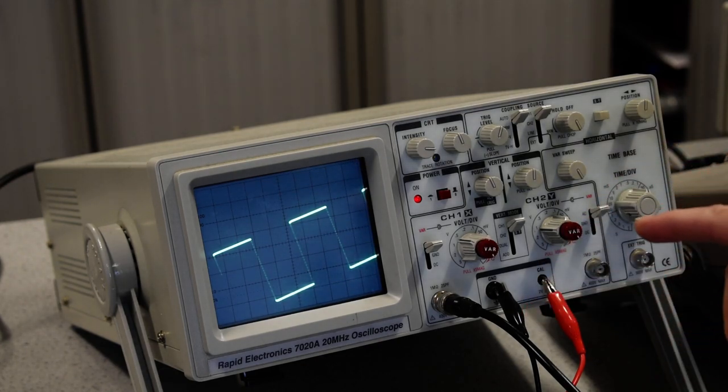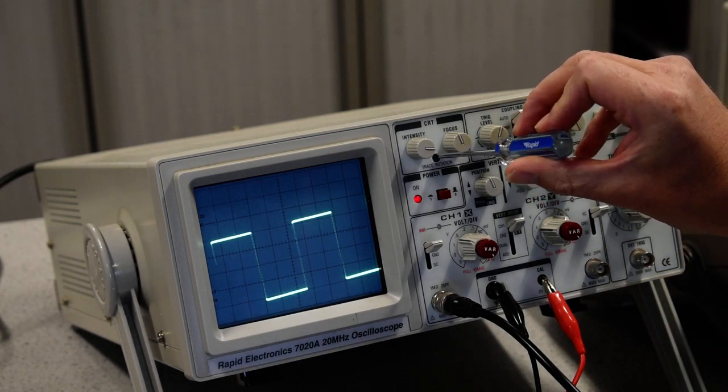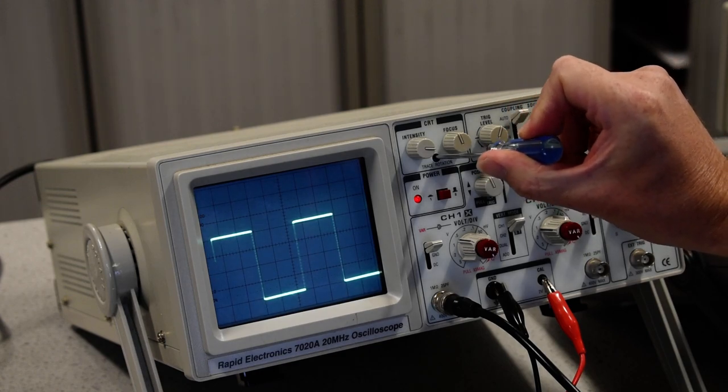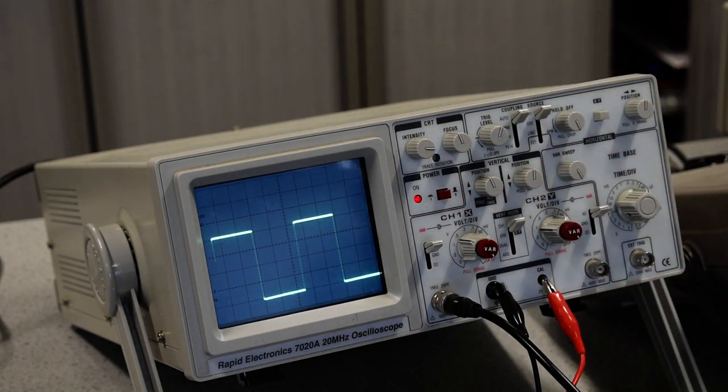At the moment the trace is offset, so what we can do is manipulate the trace rotation. There's a flat blade screwdriver and good eyesight, and get the horizontal sweeps so that it makes it much easier to measure accurately.